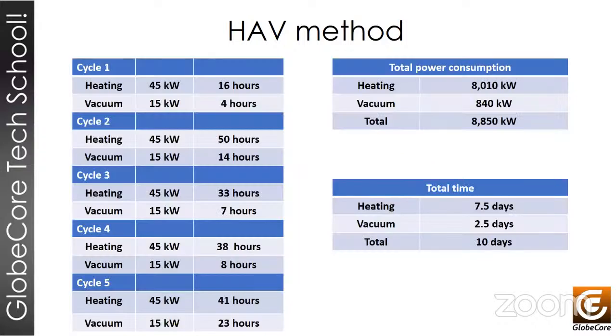You can see in the table the data of drying the winding in a vacuum using the HAV method. We see the number of cycles totaling 5. We also see the power consumption within the cycle for vacuuming and heating. In total, it took 8,850 kilowatts of power to dry the winding and 10 days of process duration. We will compare these results later.